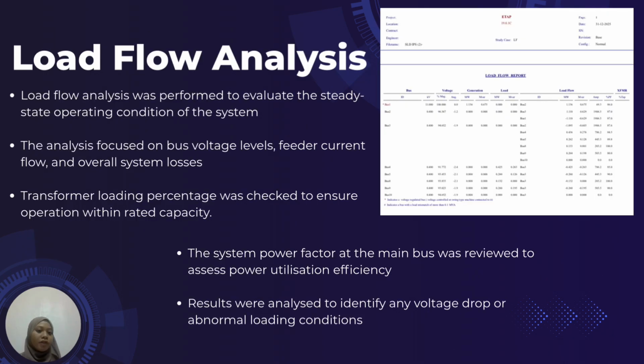After completing the system modeling, a load flow analysis was performed to evaluate the steady-state operating condition of the system. This analysis focused on important parameters such as bus voltage levels, feeder current flow, transformer loading, and overall system losses. From the results, the transformer loading percentage was checked to ensure that it operates within its rated capacity under normal conditions. The system power factor at the main distribution bus was also reviewed to assess the efficiency of power utilization in the plant.